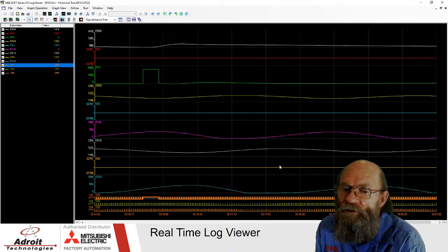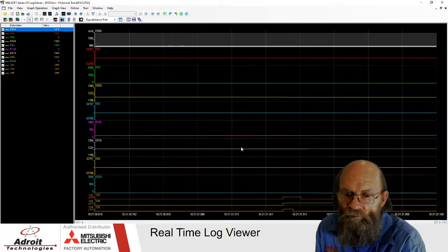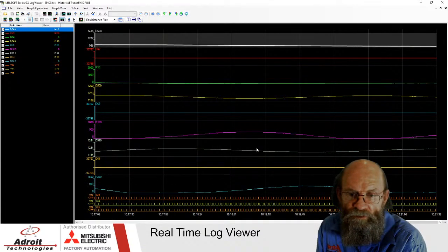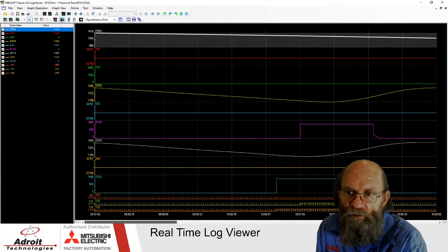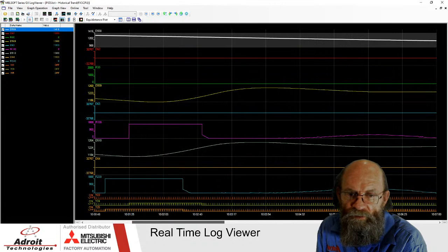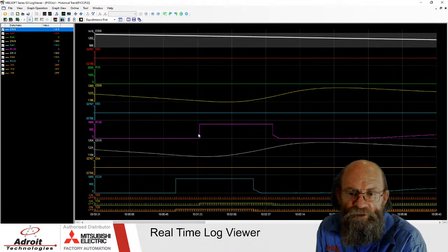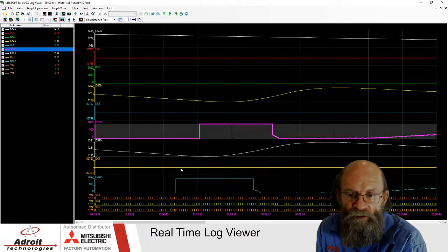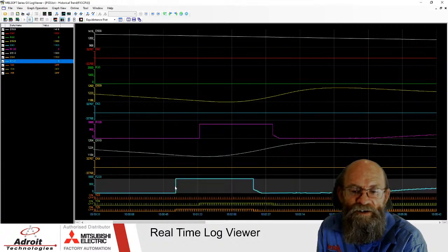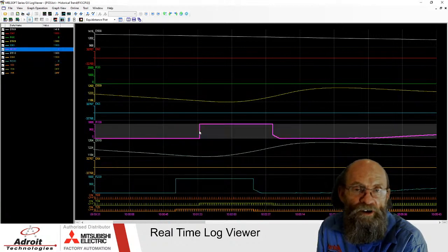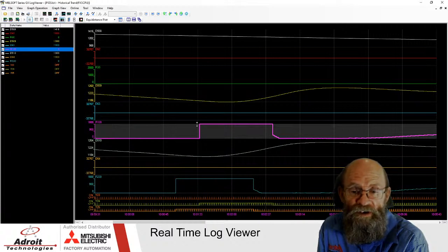That one should look a bit different. If I zoom out, what did I do here? Okay, so at this point the auto tune started over here. I can actually see my time interval from manually starting the auto tune. You can write your program obviously to start your auto tune automatically. You just grant some time for the duration for temperature changes. So the auto tune started at this point.